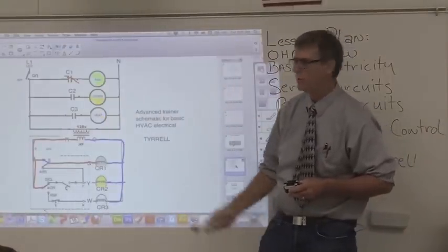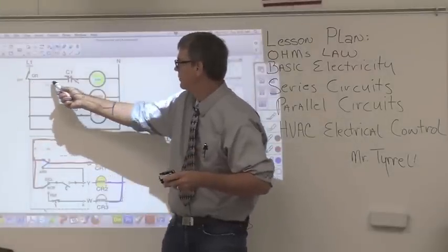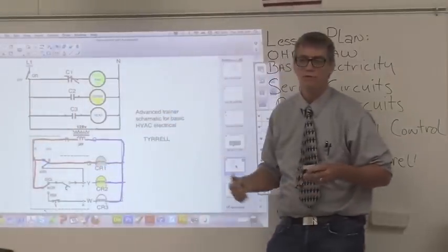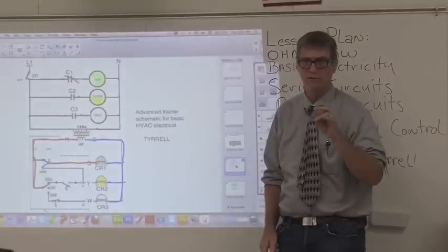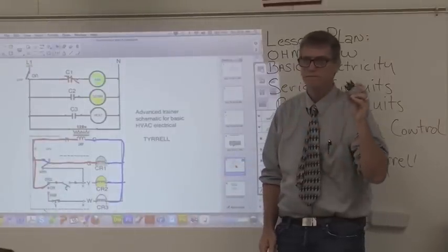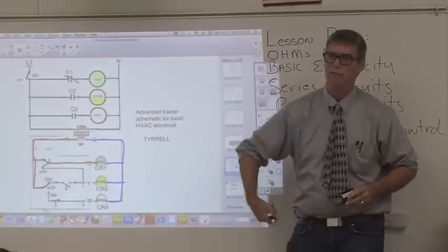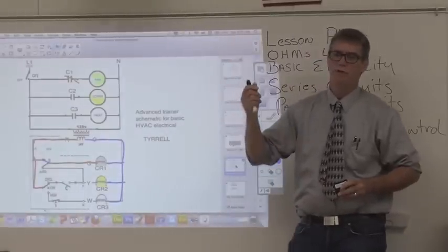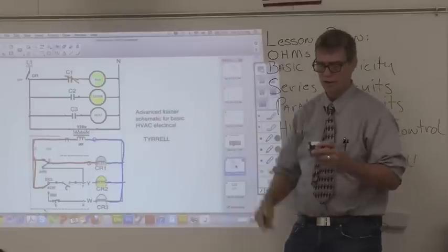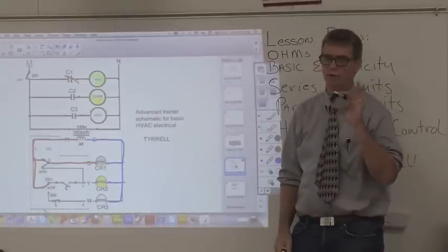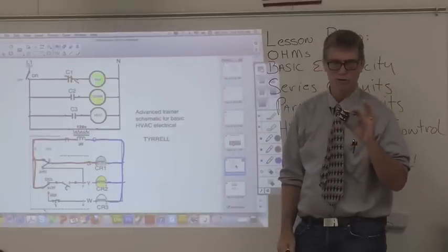When that contact closes, we're going to take that 110 to 120 volts out to the fan motor itself. That thermostat is doing the same thing as you walking into a room and turning the light switch on and bringing power to the components. But we're going to do it automatically with the thermostat and we're going to do it safely with 24 volts.